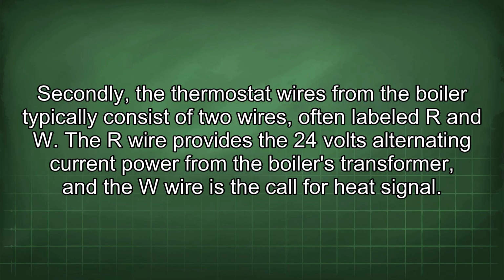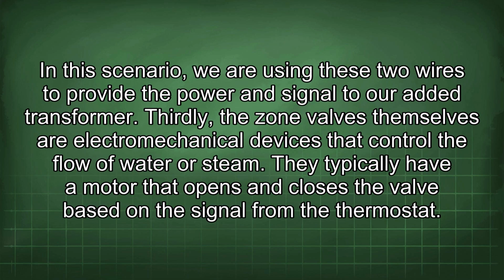Secondly, the thermostat wires from the boiler typically consist of two wires, often labeled R and W. The R wire provides the 24 volts alternating current power from the boiler's transformer, and the W wire is the call for heat signal. In this scenario, we are using these two wires to provide the power and signal to our added transformer. Thirdly, the zone valves themselves are electromechanical devices that control the flow of water or steam.